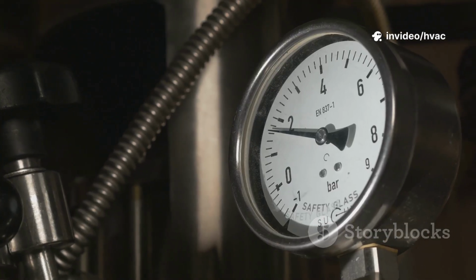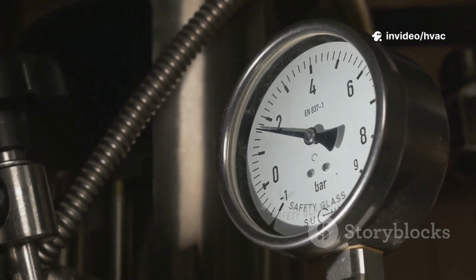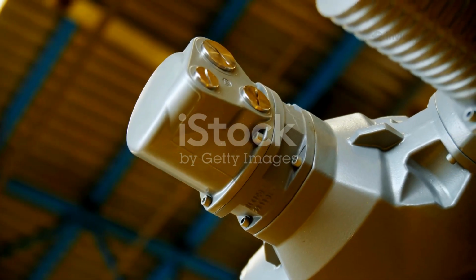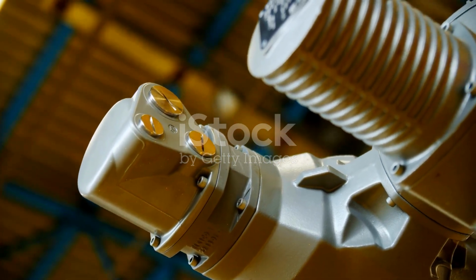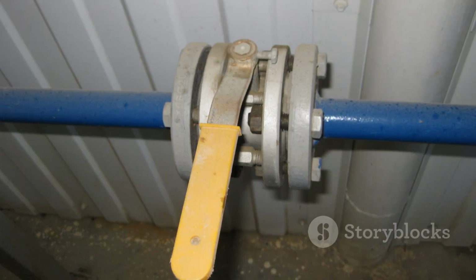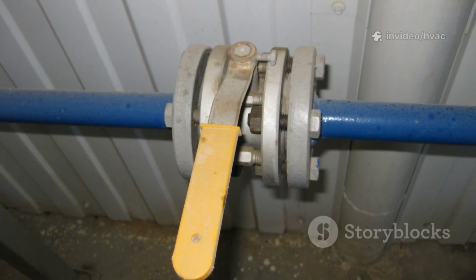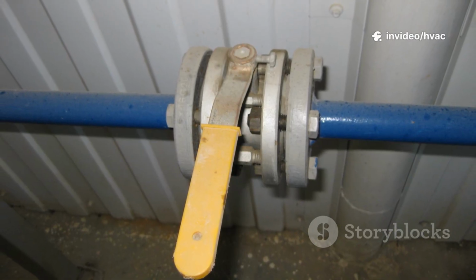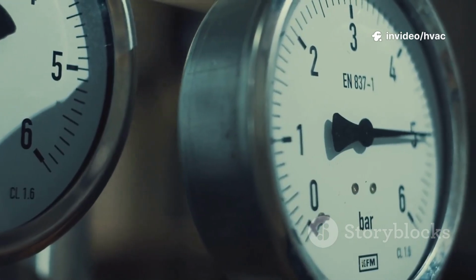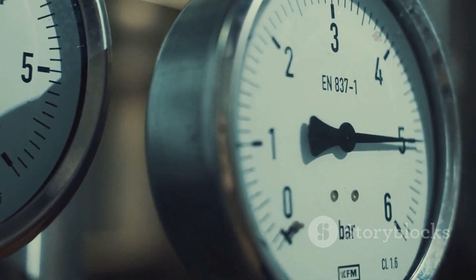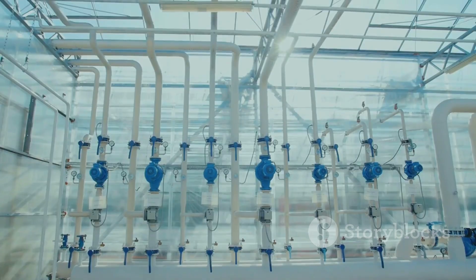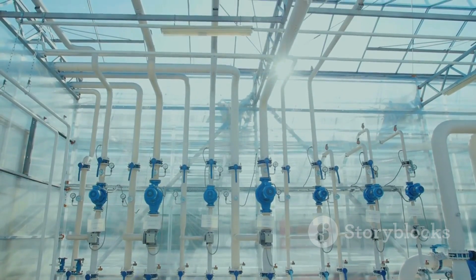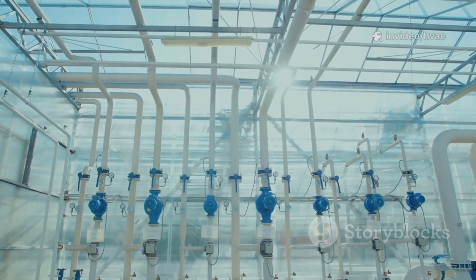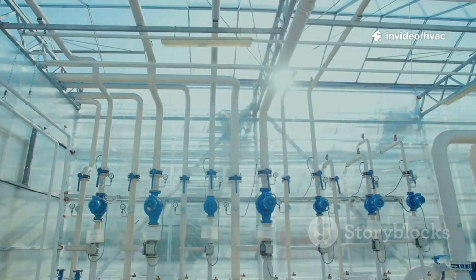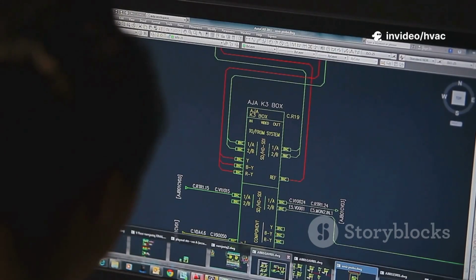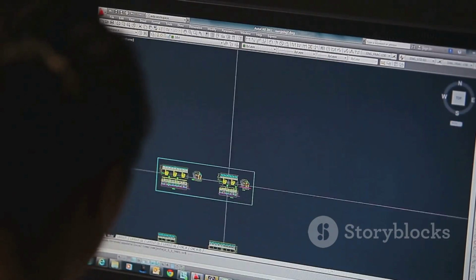Another frequent error is ignoring the minimum differential pressure requirement of the valve. Every PICV needs a certain minimum pressure drop across it to power its internal pressure regulating mechanism. If a valve is placed at the end of a long pipe run where the pressure is very low, it might not meet this minimum threshold. When this happens, the valve loses its pressure independence and behaves like a simple fixed orifice. It will no longer be able to control flow accurately, and the terminal unit it serves will likely be starved of water, leading to a lack of heating or cooling. It's critical to perform a hydraulic calculation to ensure enough pressure is available at every valve location.